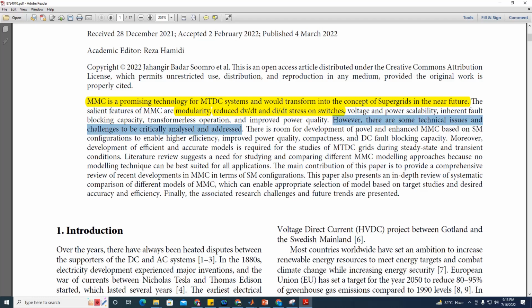As I already discussed, DC pole-to-pole short circuit problem is a very critical and challenging issue that must be addressed. Researchers are also working in this area, proposing variants of half-bridge submodules where DC fault issues can be cleared, and DC fault clearance techniques are suggested.